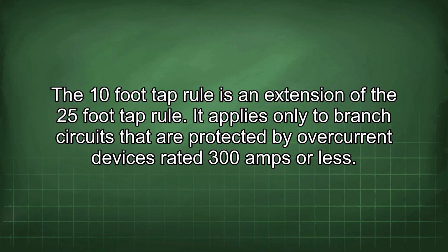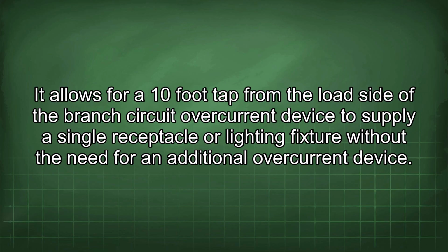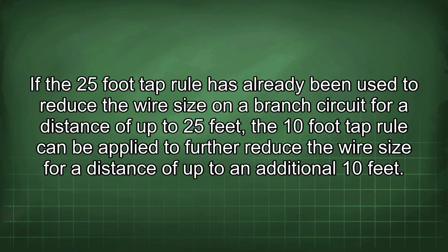The 10-foot tap rule is an extension of the 25-foot tap rule. It applies only to branch circuits that are protected by overcurrent devices rated 300 amps or less. It allows for a 10-foot tap from the load side of the branch circuit overcurrent device to supply a single receptacle or lighting fixture without the need for an additional overcurrent device. If the 25-foot tap rule has already been used to reduce the wire size on a branch circuit for a distance of up to 25 feet, the 10-foot tap rule can be applied to further reduce the wire size for a distance of up to an additional 10 feet.